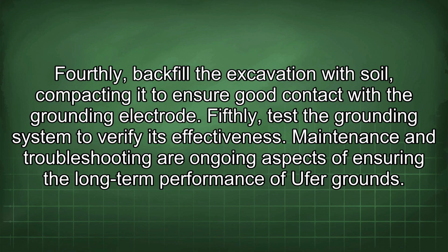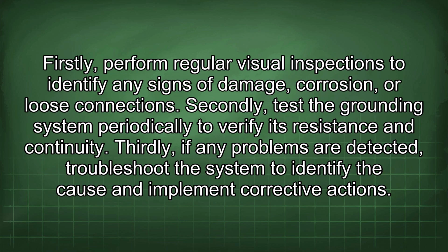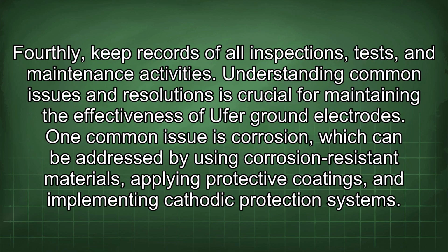Maintenance and troubleshooting are ongoing aspects of ensuring the long-term performance of Ufer grounds. Firstly, perform regular visual inspections to identify any signs of damage, corrosion, or loose connections. Secondly, test the grounding system periodically to verify its resistance and continuity. Thirdly, if any problems are detected, troubleshoot the system to identify the cause and implement corrective actions. Fourthly, keep records of all inspections, tests, and maintenance activities.